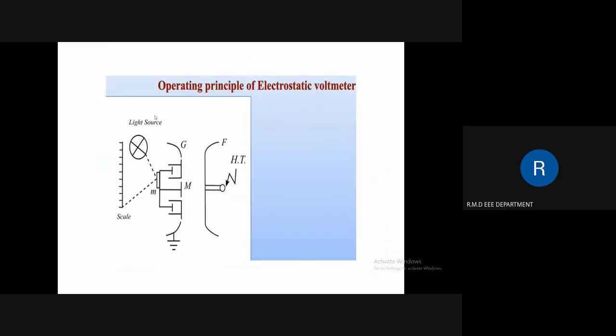The cap or dome encloses the balance and the moving disc. Now the operation of this electrostatic voltmeter: the balance beam carries a mirror which reflects a beam of light. The movement of the moving electrode is amplified through this optical arrangement. To measure the given voltage with precision, the disc diameter is increased and the gap distance between the electrodes is minimized. As the gap is larger, the uniformity of the electric field is maintained by the guard ring G placed between the electrodes F and M using a capacitance divider.